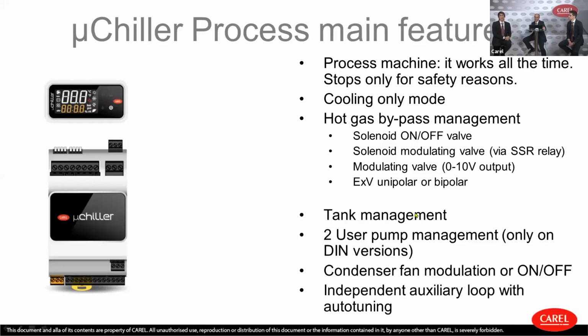It's about the independent auxiliary loop with auto-tuning. That's a very interesting feature because it gives you the freedom to manage an independent regulation. For example, your chiller is meant to regulate the outlet or inlet water — supply, return — because the chiller makes cold water. But then you might need a thermostat, or to regulate a modulating user pump, and your needs might differ from project to project. So we thought: why not give a regulation that's completely independent from the main one, with its own PID parameters set up independently, plus the addition of auto-tuning.